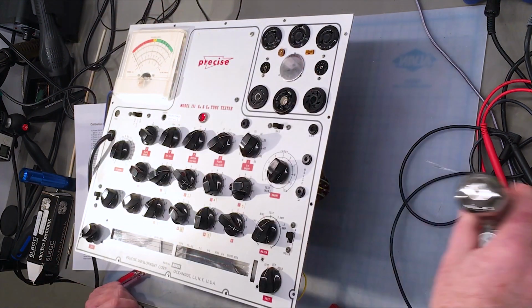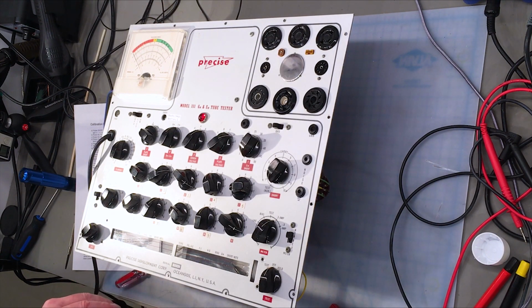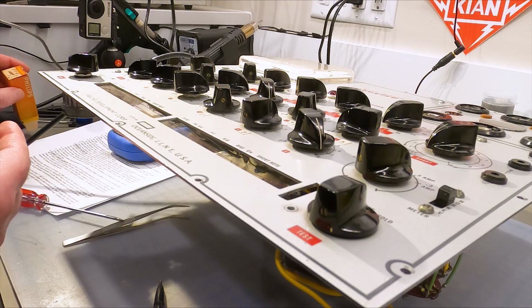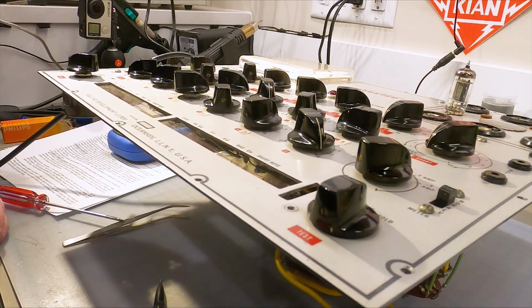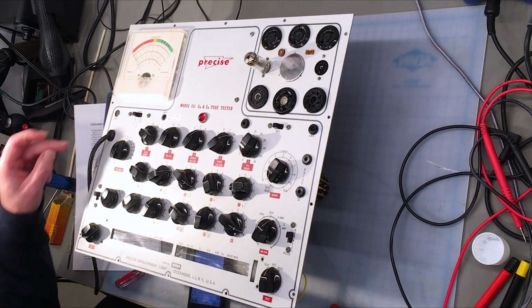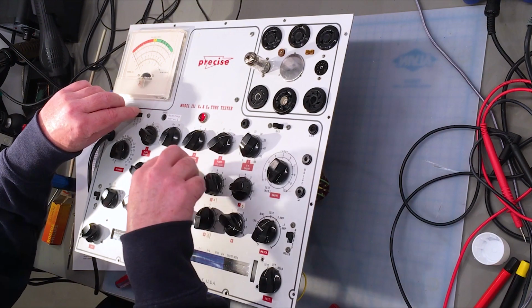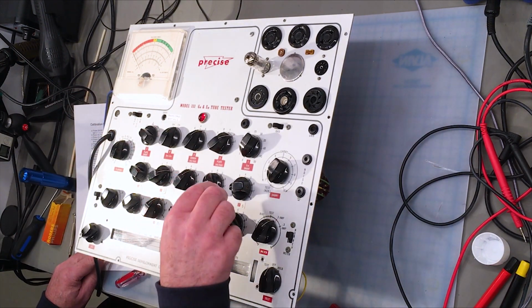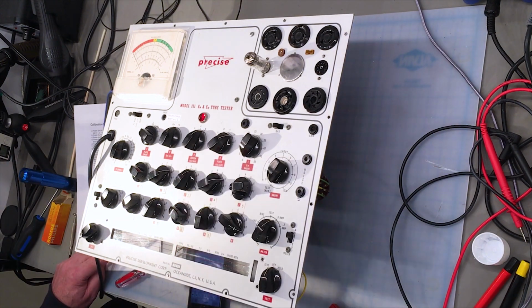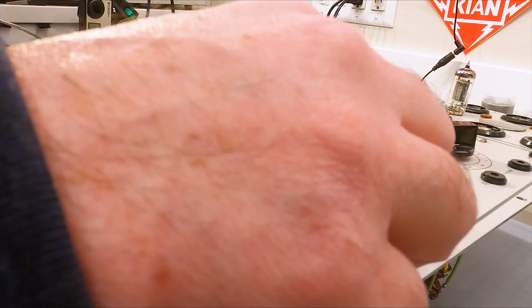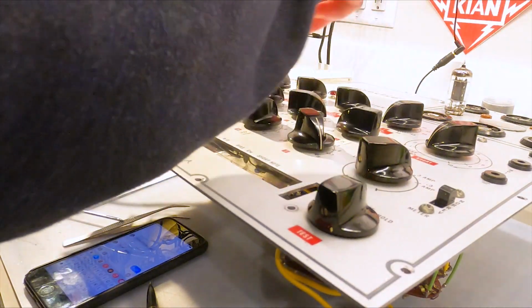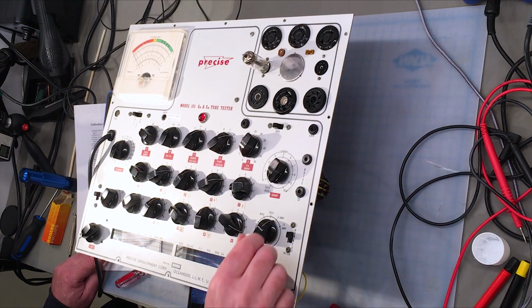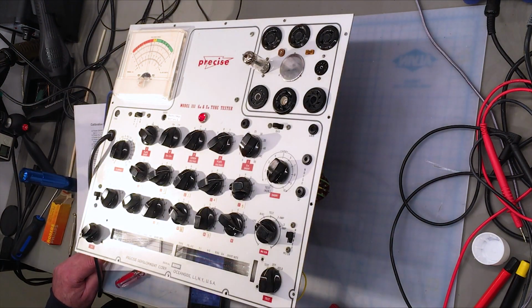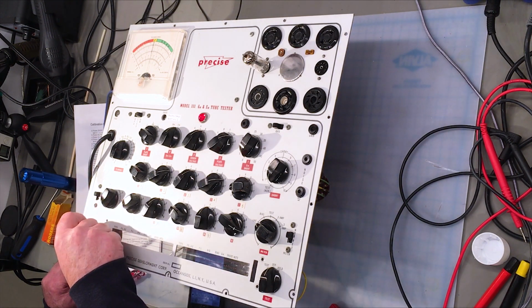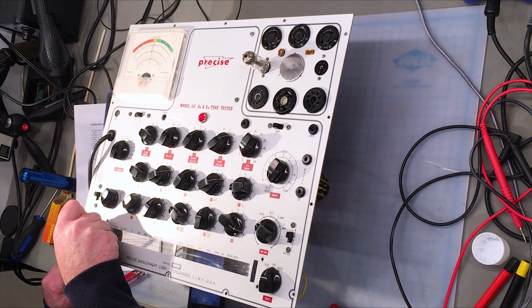Gently extract the tube, and we'll insert the 6C4. Here we go. Then what we do is we rotate switch H to 5, and switch I to 6. Make certain the test switch is in the off position. Filament switch should be at 6.3, and insert the 6C4, and we have. Meter switch should be at line, and we should be able to adjust line voltage, and we'll do that. And line voltage is coming down as tubes heat up a little bit.